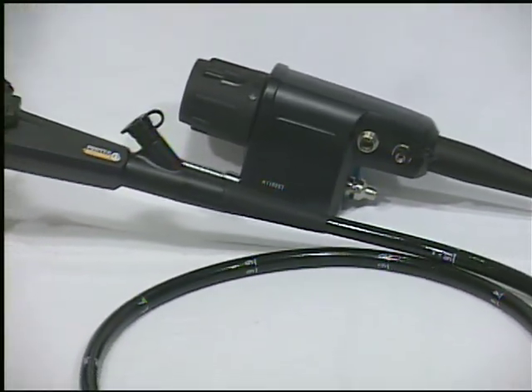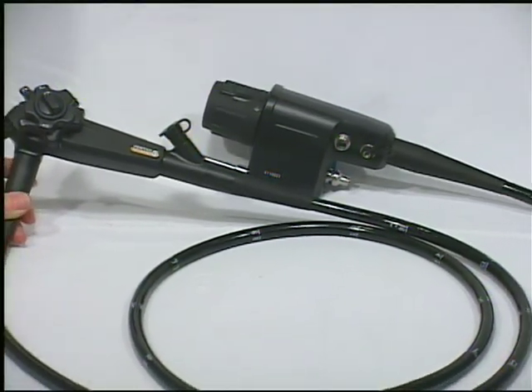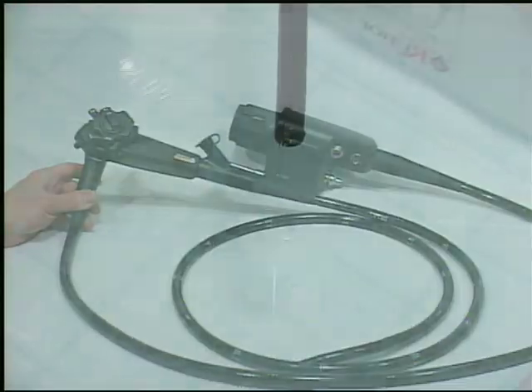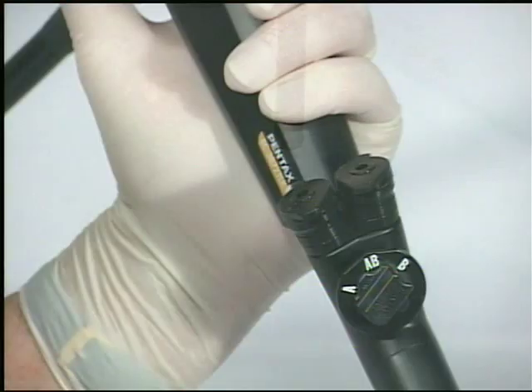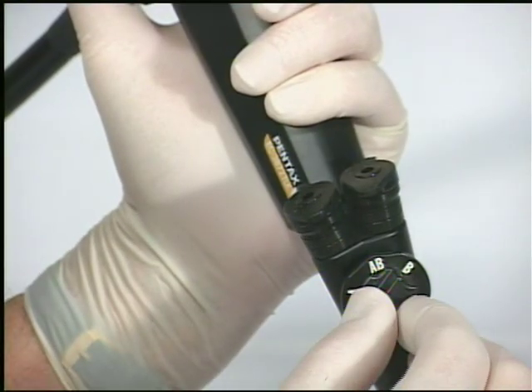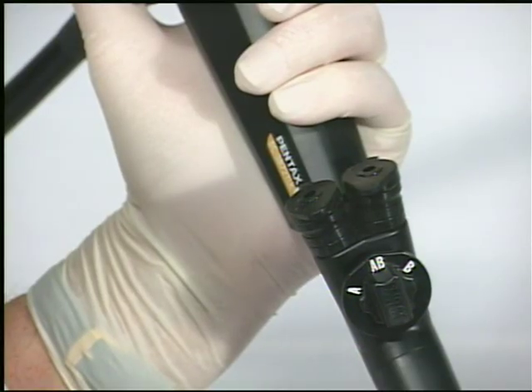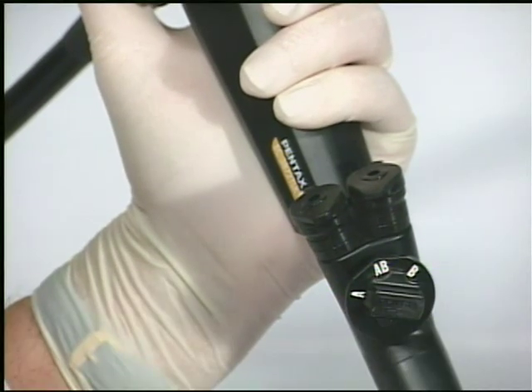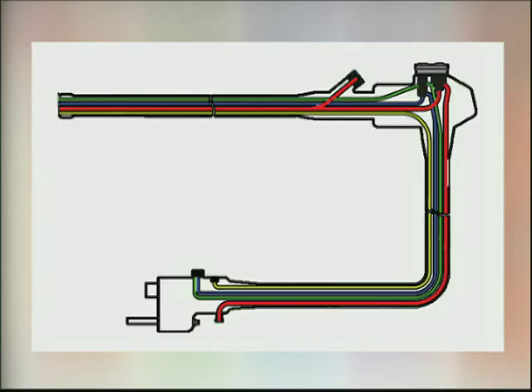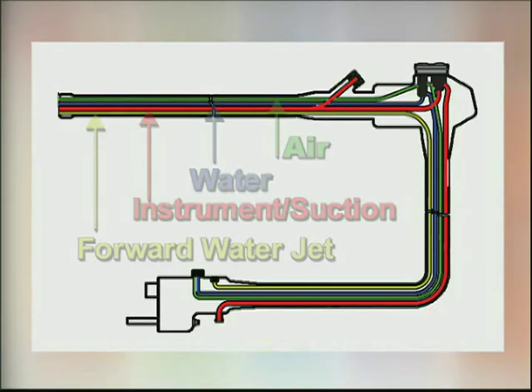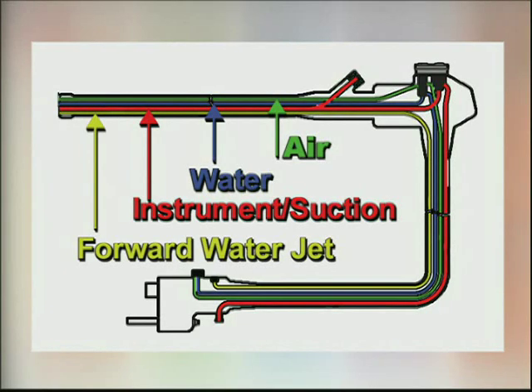Pentax 70, 72, and 70K, 72K colonoscopes also contain a forward water jet channel and/or a secondary biopsy channel, all of which must be properly cleaned and high-level disinfected or sterilized. Reprocessing instructions will now be reviewed for more complex Pentax gastroscopes and colonoscopes that have anywhere from 4 to 5 internal channels. These color-coded internal schematics illustrate the independent forward water jet channel on a Pentax colonoscope.